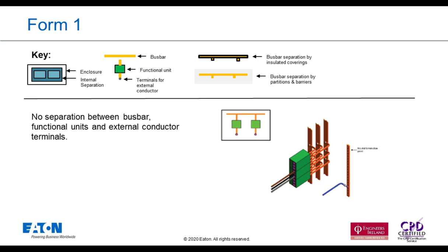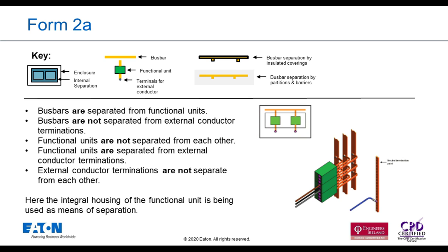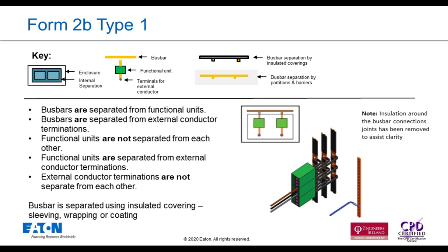So Form 1, again, as you can see, there's no separation between the bus bar, the functional device, and the outgoing cables. Form 2A, although it looks exactly the same as Form 1, what we're using is the housing of the functional unit as a means of separation from the main bus bar. And you've got Form 2B. Again, we're still using the housing of the functional unit as a means of separation from the main bus bar.